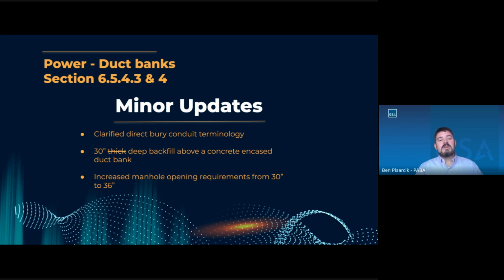Likewise, the second bullet, 30 inches thick backfill above a concrete encased duct bank. Some interpreted that as we wanted 30 inches of concrete above a concrete encased duct bank, which is certainly not what we wanted. So we changed the word thick to deep. Hopefully that'll make more sense. And we increased the manhole opening requirements from 30 inches to 36. I think that came in from industry as a suggestion.